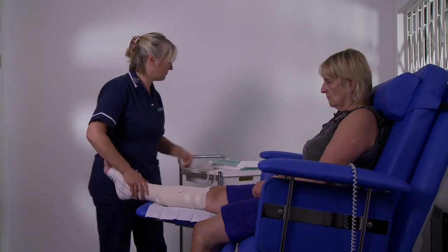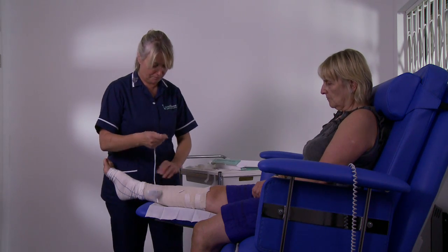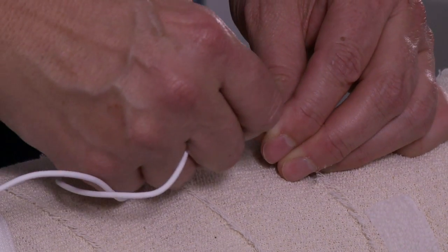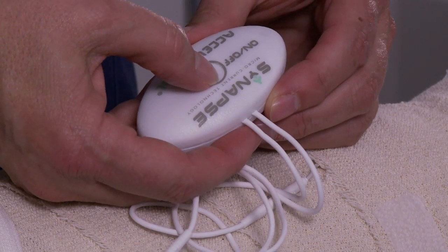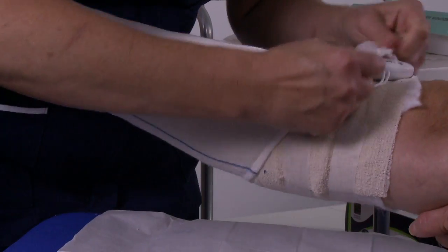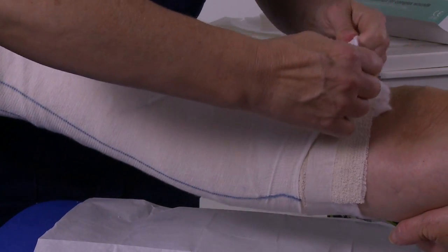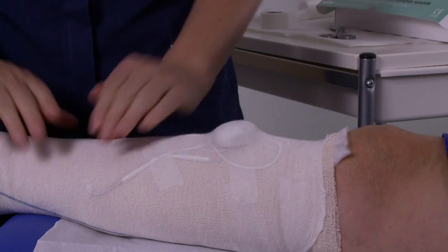Accel-Heal is a non-invasive, compact, Class 2A medical device used alongside standard dressings. It is a 12-day treatment course consisting of 6 battery-powered 48-hour single-use devices applied consecutively. It uses the patented Synapse Sequence, programmed to deliver a specific series of electric energy interactions through the skin to manipulate gene expression in order to modify specific physiological functions in dermal tissue.